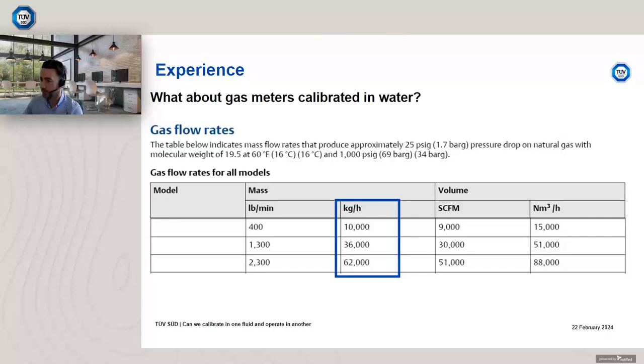We can see here, again, I've taken out the model number, but these are 2, 3, 4 inch devices, and you can see that the gas flow rates are remarkably smaller. So 10,000 for the 2 inch up to about 62,000 for the 4 inch. And obviously don't expect you to remember it, but those gas flow rates are approximately 20% of the liquid mass flow. So what happens if we chart this?